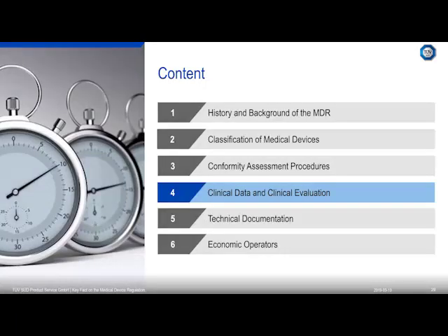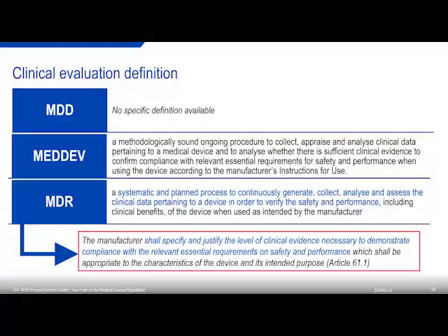I think the most critical topic under the MDR will be the clinical data and the clinical evaluation. So 50% of the MDR is talking about clinical, which means that clinical might not have had the focus under the MDD, AIMDD that it will have now. That's also very well illustrated by what a clinical evaluation is. The MDD in the beginning didn't have a specific definition of a clinical evaluation. So what was done? A MEDDEV document was created.